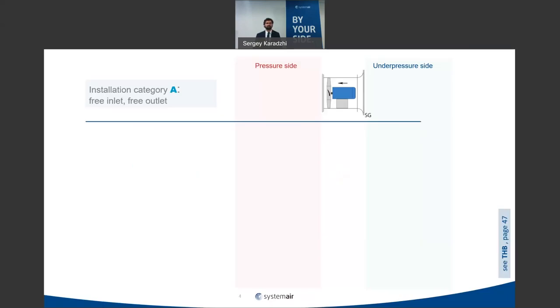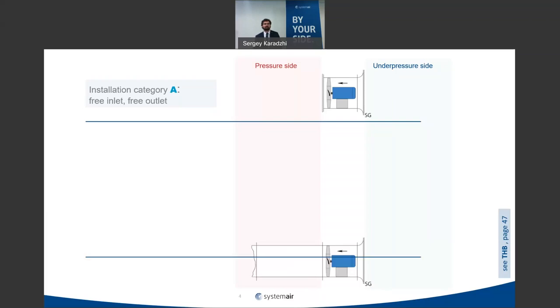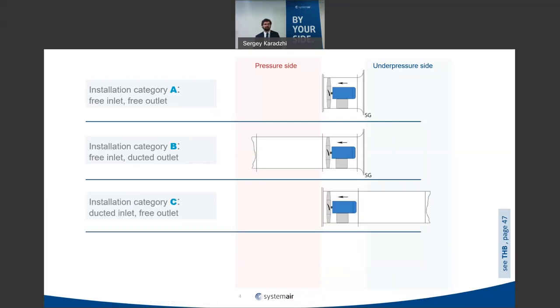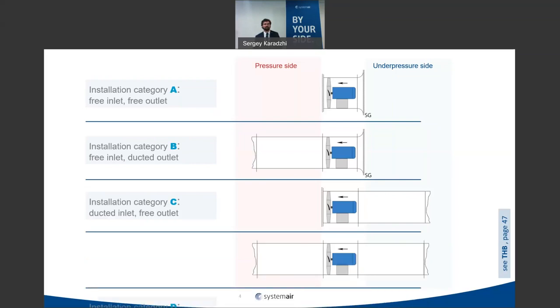First, installation categories. As most of you probably know, in the ISO 5801 and 210 standards, four installation categories are described: Category A — free inlet, free outlet; Category B — free inlet, ducted outlet; Category C — free outlet, ducted inlet; and Category D — ducted inlet and ducted outlet. It is also recommended in the standards to test the fan in the installation category closest to its future usage.